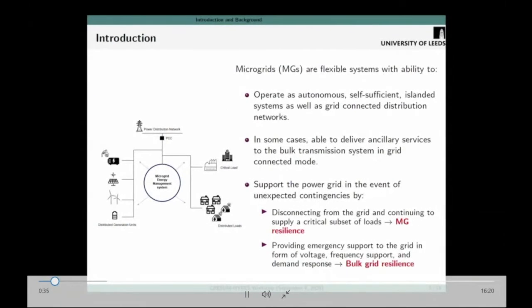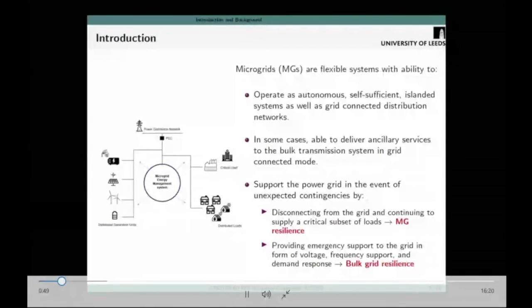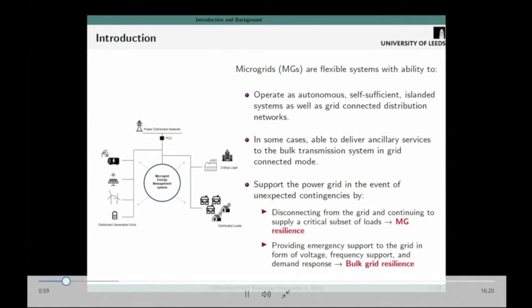Microgrids are flexible systems as they are able to operate when connected to the main grid network, usually the distribution power network, or as self-sufficient islanded systems. In some cases, they are able to deliver auxiliary services to the transmission network as well. In case we have a major contingency in the bulk network, caused maybe by a major fault or a hazard, the microgrid can disconnect and form an island able to serve, especially the loads in the network.